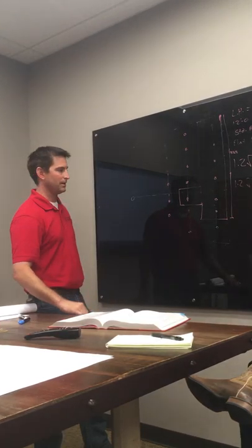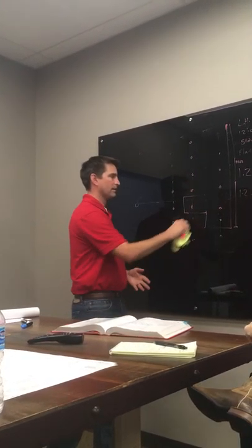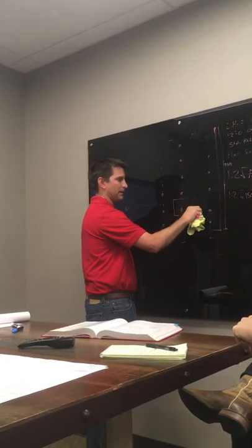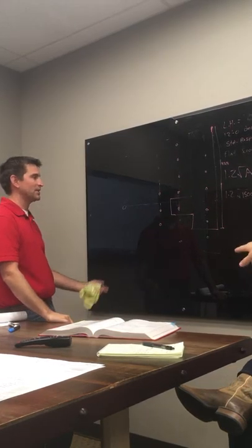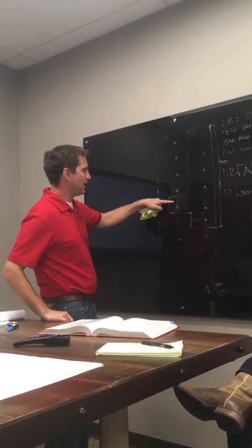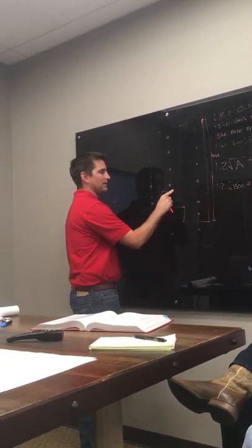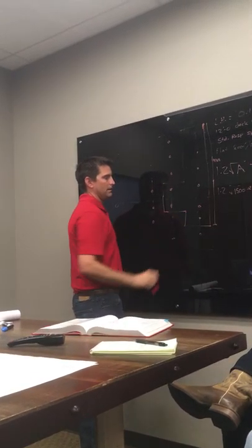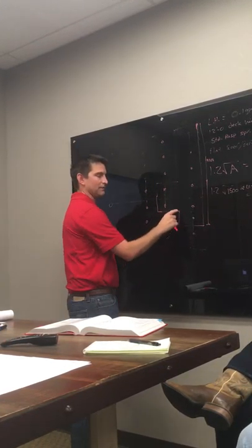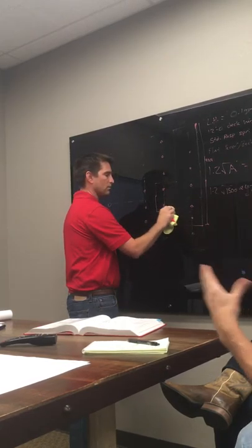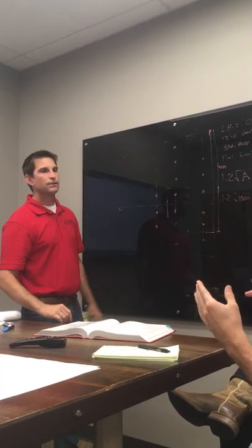Now what's the next head I pick up? You work out of the branch, right? So I'm gonna pick the head closest to the main and work my way out. So whichever one's closer, the top or the bottom? The next closest to the main, yeah. So is this one closer to that main, or is that one closer to the main? Looks like the top one's closer. So actually that one is, right? So now I'm actually going to pick up this one. Then now I'm going to jump back down and pick up this one. That's okay. So you don't do it in order. Once you pick the adjacent branch, you don't always work down the branch. You always look for the closest one to the main first.